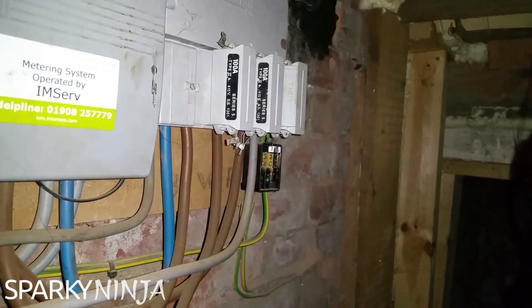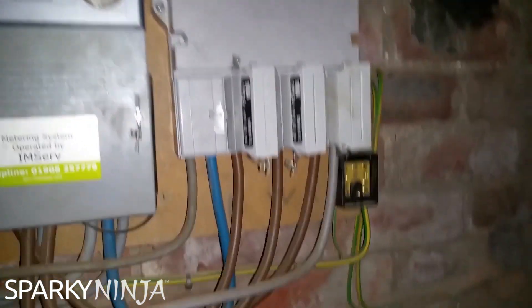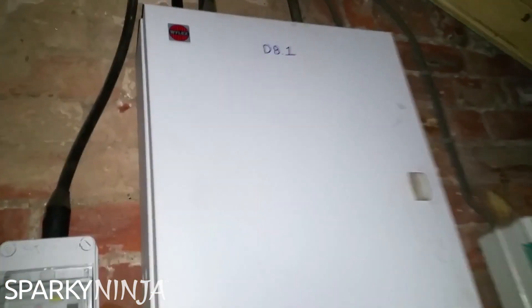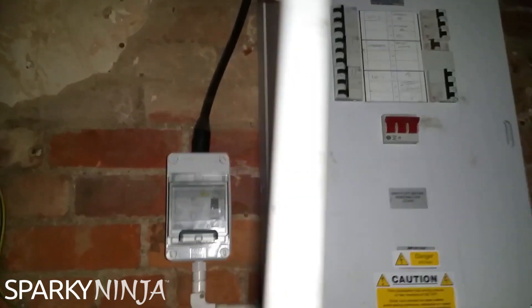We're doing a test on a car garage today. There's an intake coming in, fairly new, past few years. Someone's tapped into the earth — this was an old TT system and they've put in a new supply, but they haven't put in a PME. With no PME, this is still TT. The problem is an electrician has come in, put in distribution with no RCDs, and there's no RCD in line with the supply.